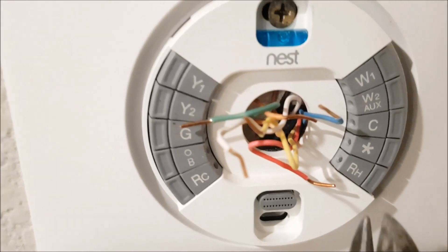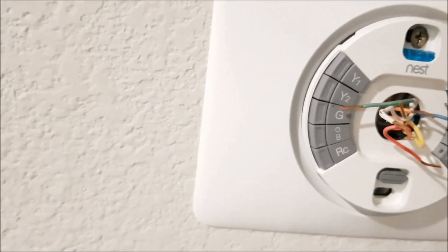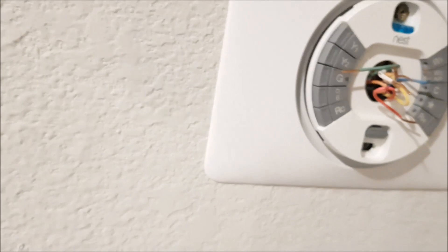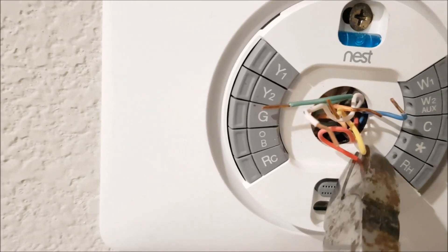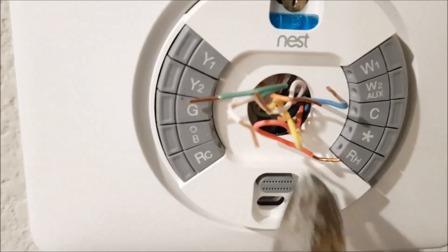Now we connect the wires the same way we had them. The red goes to RH — be careful, there's RC and RH; the red always goes to RH. The yellow goes to the Y1 terminal, the green to G, the blue to C. The orange goes to O/B. You can use a pair of pliers to help. Press the terminal release, then push the wire through — once you press it, it releases and you push the wire in.